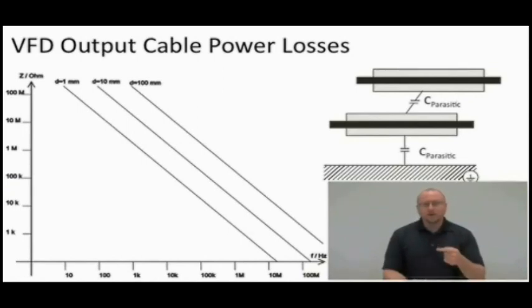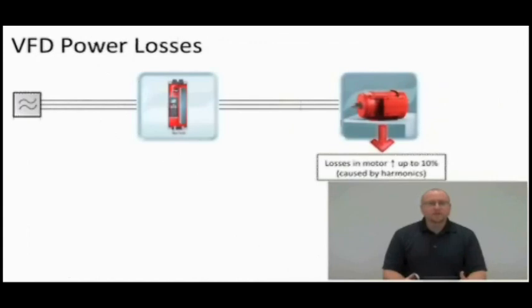So in between power cables acts like a capacitor, and in between the power cables and ground, that also acts like a capacitor. So you could have some losses there. More importantly, it's an electromagnetic compatibility issue that you could have some interference with other components, but it could be a power loss in the system.